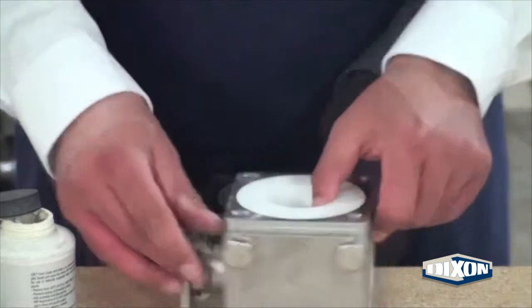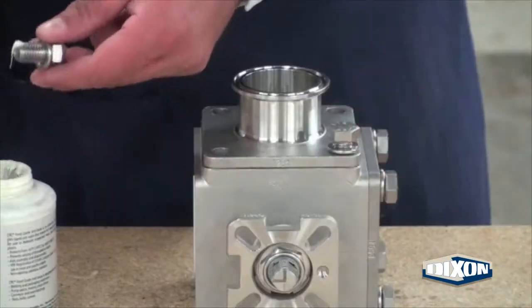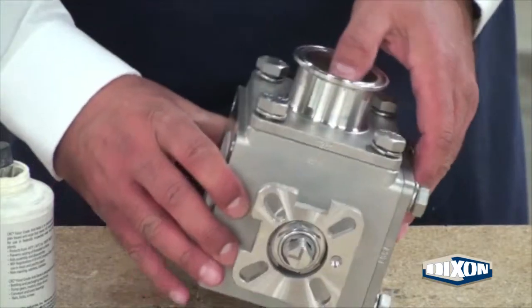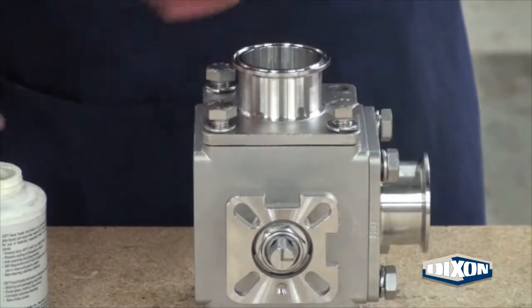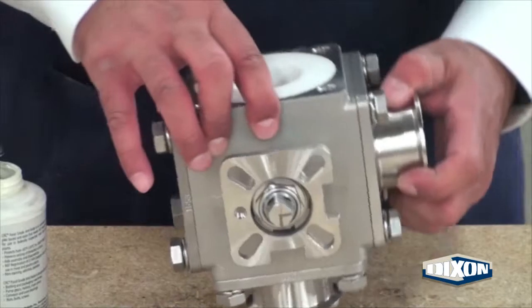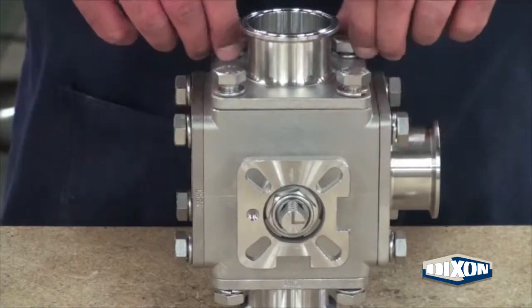Rotate the valve body 90 degrees and align the clamp end port ID with the ID of the ball. Apply food grade anti-seize to the bolts and hand tighten. Rotate the valve body 90 degrees and repeat the procedure with the next end. Rotate the valve body 90 degrees again and rotate the valve stem for visual alignment, then repeat the procedure with the remaining clamp end.